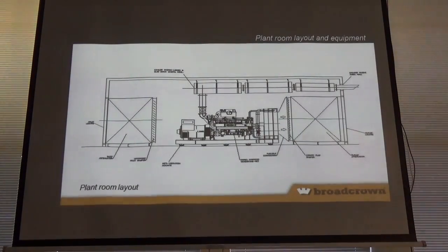If you're going into that plant room, you'll need to attenuate. That pull pusher fan will draw air in from the path of least resistance. Given your discharge temperature, you have to duct it away, because the last thing you want is it recirculating and then shutting down the engine. It's effectively derating it, drawing in higher ambient. Okay, so you need to duct that discharge system away.